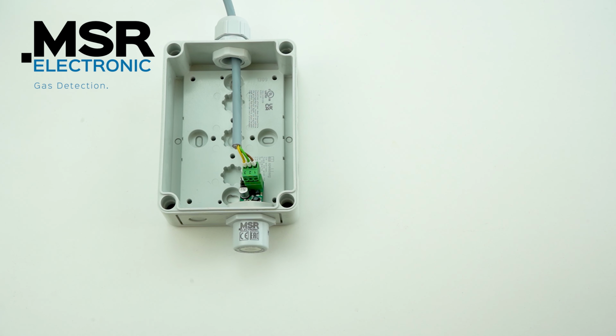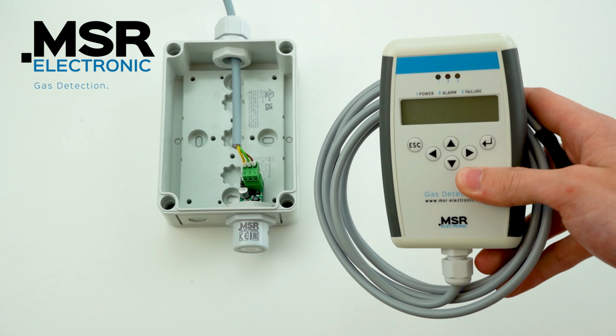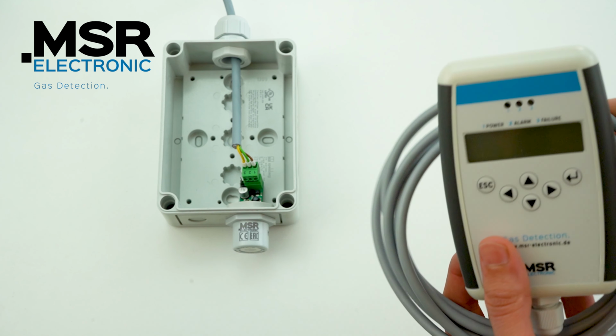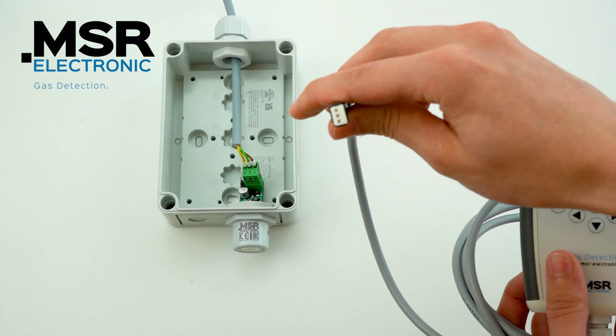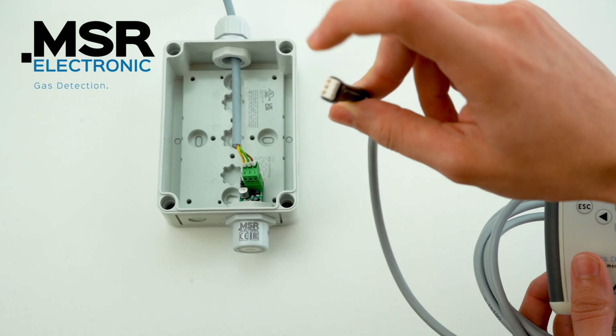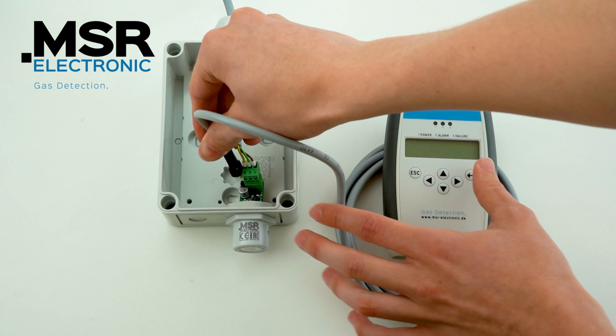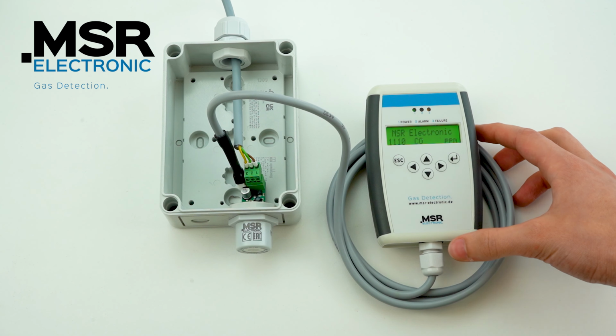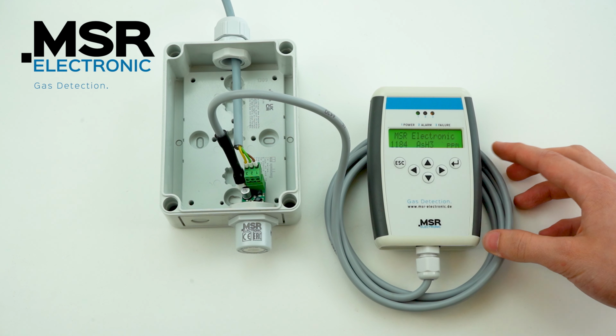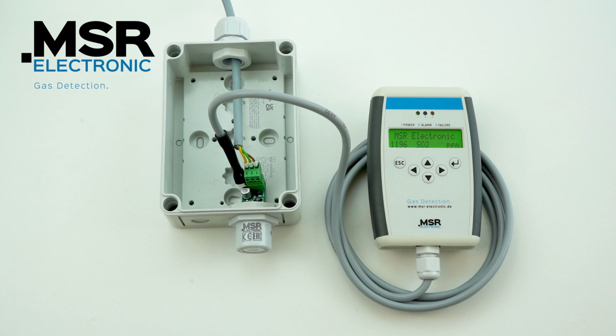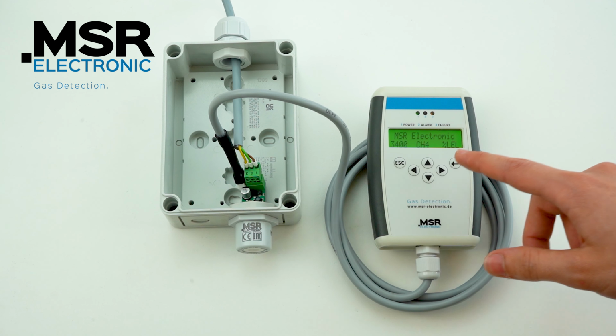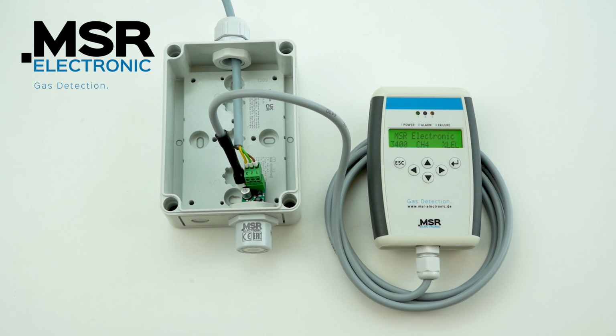Now we need the tool STL06MC2, which has a 3-pin plug with 2 lugs on the side. When plugging it into the analog sensor, it is essential to align the 2 lugs with the side of the green clamp, otherwise the polarity will be reversed. If the connection is successful, the correct gas type is automatically selected. After the warm-up time has elapsed, the measured value of the sensor is displayed and you can start calibrating the sensor.